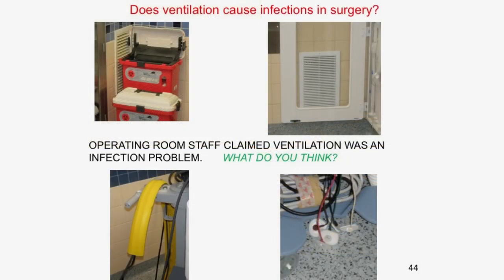So we want to avoid that, as well as on slide 44, avoid stacking things in front of the return ducts. Pay more attention to stuff that matters, like whether you're keeping your cardiac patches on the floor, or your Da Vinci device with the electrical protection pads over the tops of the handles. That's just bad practice. So it's not ventilation in this case. The ventilation is there, but the staff doesn't understand how to use it.